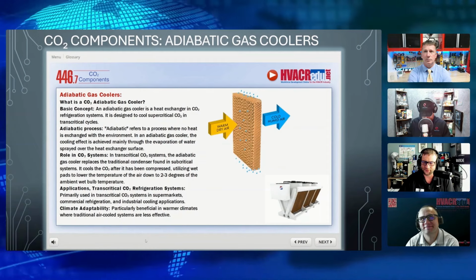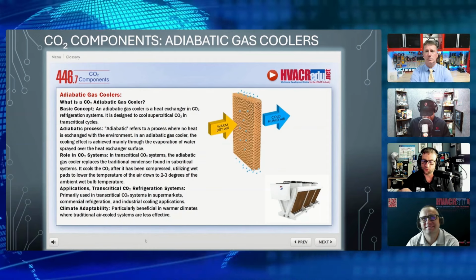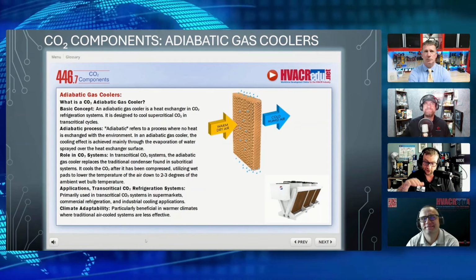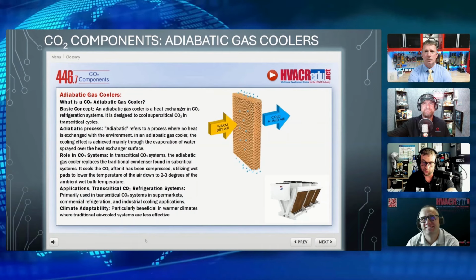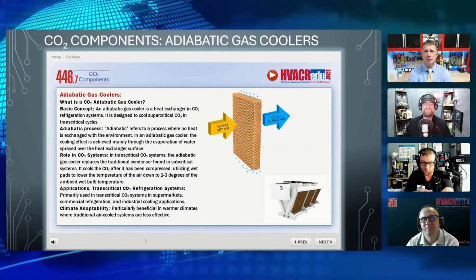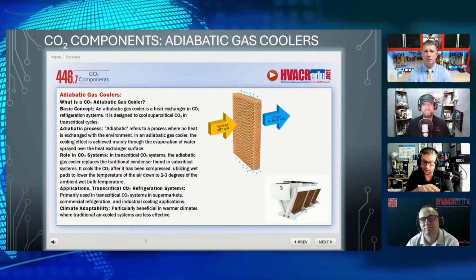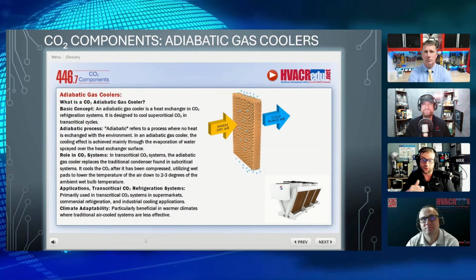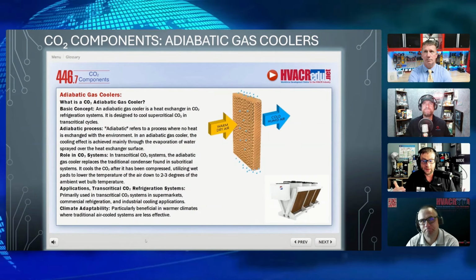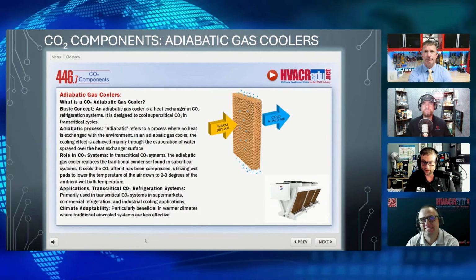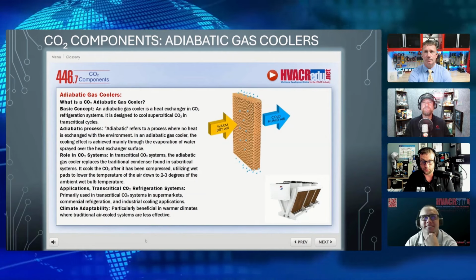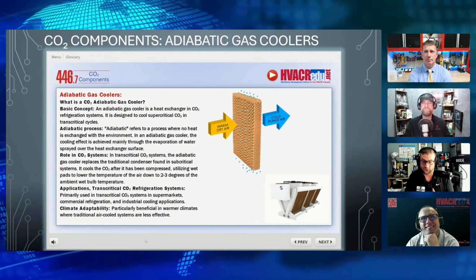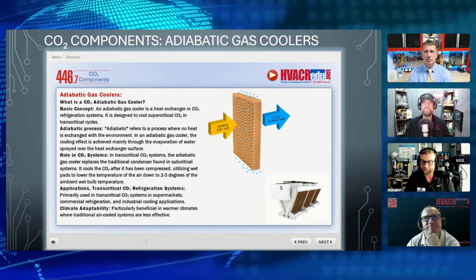Wisconsin still gets above the 80s, because we stated before, like with the TD, if it does have a 5-degree TD, once you get to 82 degrees, even with a low TD adiabatic gas cooler, you're still going to run right at transcritical, right? So some place where it doesn't get 82 degrees, we could potentially run subcritical all year round.